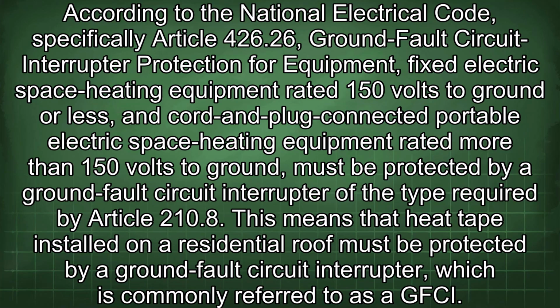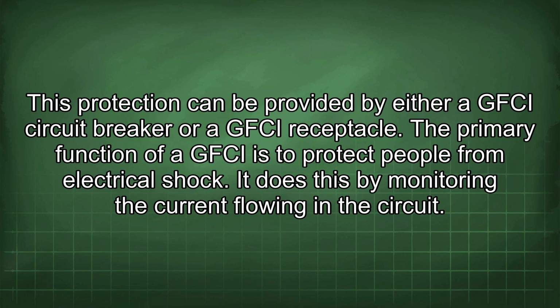According to the National Electrical Code, specifically Article 426.26, ground fault circuit interrupter protection for equipment, fixed electric space heating equipment rated 150 volts to ground or less, and cord and plug connected portable electric space heating equipment rated more than 150 volts to ground must be protected by a ground fault circuit interrupter of the type required by Article 210.8. This means that heat tape installed on a residential roof must be protected by a ground fault circuit interrupter, which is commonly referred to as a GFCI. This protection can be provided by either a GFCI circuit breaker or a GFCI receptacle.